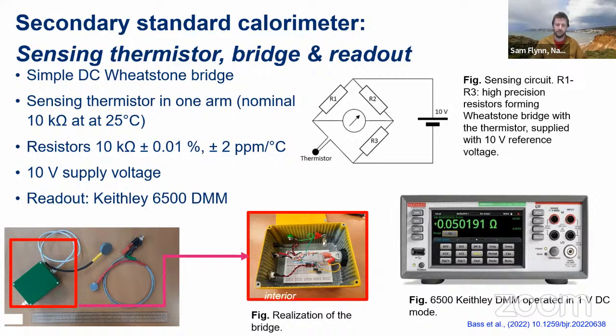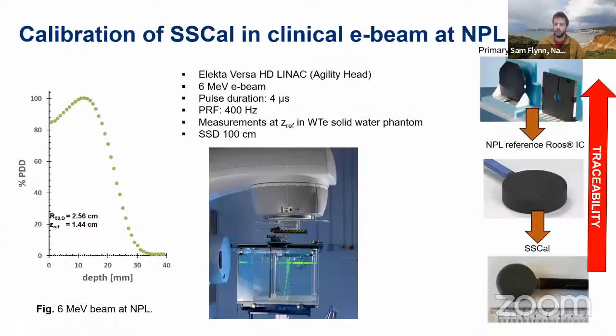We calibrated this in terms of temperature, and then we placed it in a water tank, in solid water in front of our electron linear accelerator. So we've got one linear accelerator at NPL that we use for our calibrations for all the different services we provide. And yeah, we calibrated this secondary standard calorimeter against a Roos chamber, which was calibrated against the primary standard electron calorimeter. We did it as if it was a Roos chamber. Obviously it's not, it's got different designs and whatnot, but it's got the same water equivalent thickness building up to it. Yeah, otherwise that works well.